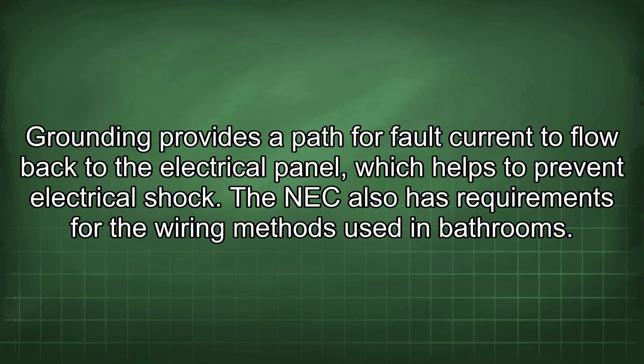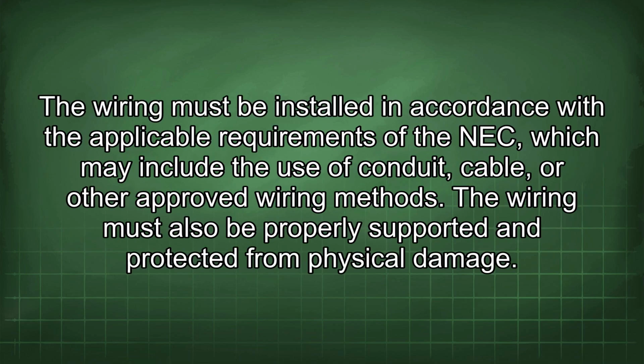Grounding provides a path for fault current to flow back to the electrical panel, which helps to prevent electrical shock. The NEC also has requirements for the wiring methods used in bathrooms. The wiring must be installed in accordance with the applicable requirements of the NEC, which may include the use of conduit, cable, or other approved wiring methods. The wiring must also be properly supported and protected from physical damage.